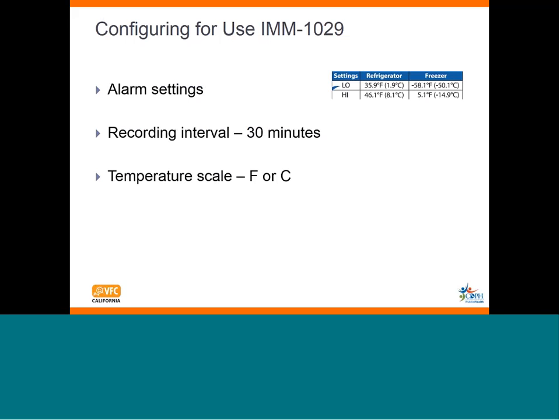Just as important, when you're setting up or configuring your device, make sure you use the same temperature scale on the device as you're going to use on the temperature log. So if you set your device up in Fahrenheit, the temperature log you complete should correspond and be in Fahrenheit.